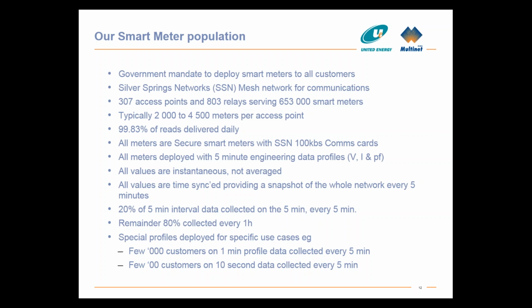We've deployed Sensor IQ to each and every one of our smart meters, with 5-minute interval data collecting voltage, current, and power factor from all of them. Those values are all instantaneous, not averaged, so we get a time-synced snapshot of what the network looks like every 5 minutes — a really good platform for any analytics. To facilitate some of our real-time analytics, we've extended that to reading 20% of our population every 5 minutes, so it's not just logged but also read every 5 minutes. The remainder, the other 80%, we bring back every hour.